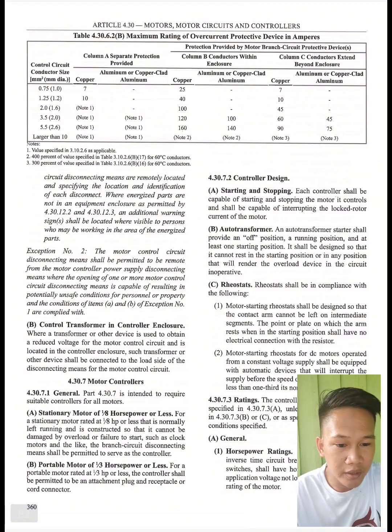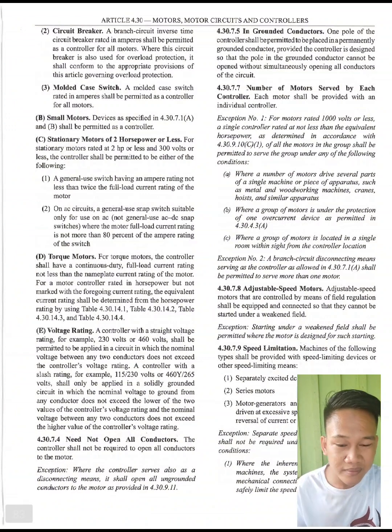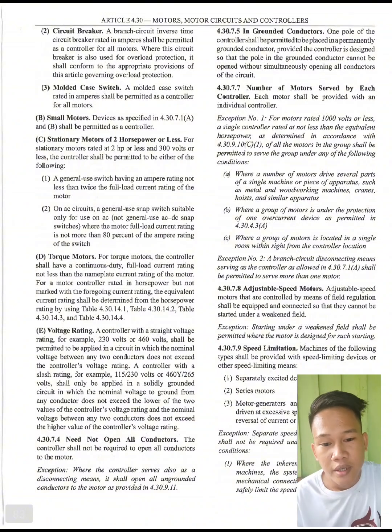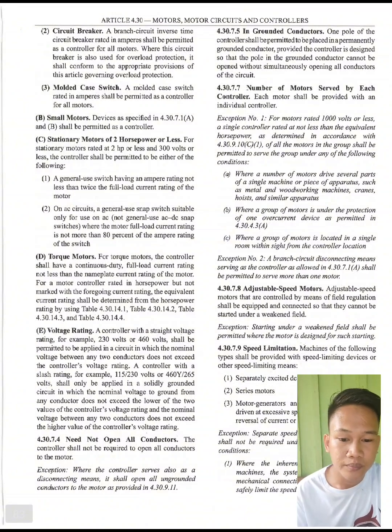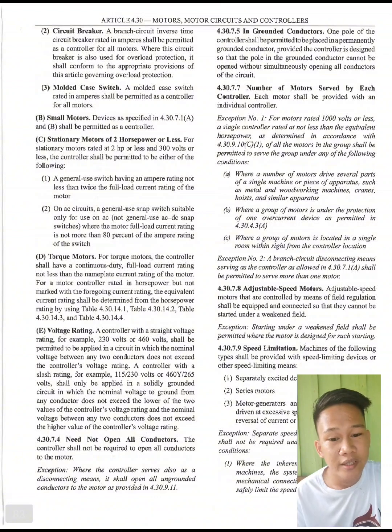So, under the conditions specified, A. General horsepower ratings. Controllers other than inverse time circuit breakers and molded case switches shall have horsepower ratings at application voltage not lower than the horsepower rating of the motor. Next we have second, circuit breaker. A branch circuit inverse time circuit breaker rated in amperes shall be permitted as a controller for all motors. Where this circuit breaker is also used for overload protection, it shall conform to the appropriate provisions of this article governing overload protection.